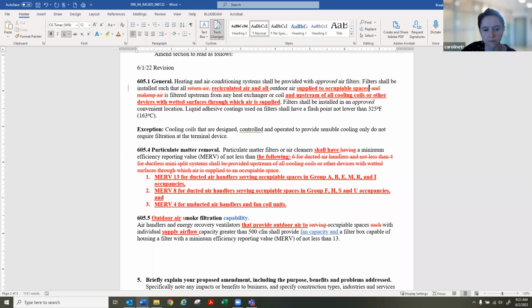Valerie. So in 605.1, you say provided with an approved air filter. Are you saying 605.4 is the approved air filter? And yes. Okay, and you're requiring a MERV 13 in our occupancies and all these other listed that you have. Then you go down to outdoor air 605.5, should be provided in 500 CFMs or more. So that really only includes group two, which is F, H, S, and U, because all the other ones actually already have to have it. So that's kind of confusing.